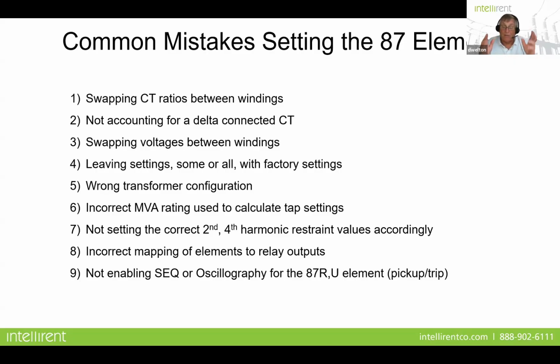People will go in, test a relay, put it in service, energize the transformer, and it immediately trips because they left it with factory settings. And I'll tell you this, 100% of the time, factory settings are not going to equate to the right settings that you need. And that may be some of the settings, it may be all of the settings. And it could be that you thought that the engineer put the settings in the relay properly, but he didn't, or you may have a file that got corrupted when you tried to write that file into the settings program. So that's one of the things.